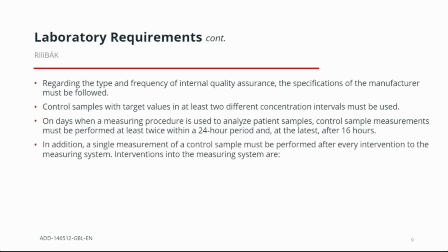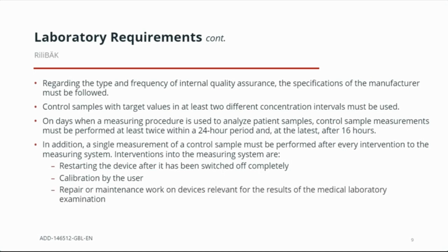In addition, a single measurement of a control sample must be performed after every intervention to the measuring system. That includes after restarting the device once it has been switched off, calibration, after repair or maintenance work that is relevant to the method's test, and changing reagent lots. In addition, control samples must be as similar as possible to the patient samples being examined. They reiterate that control and calibrator materials must not be identical. And similar to past requirements that we've discussed, control samples with known target values should be relevant to the measuring interval for our medical decisions.